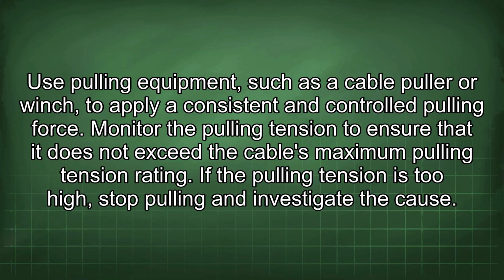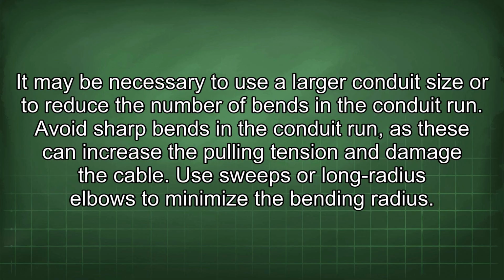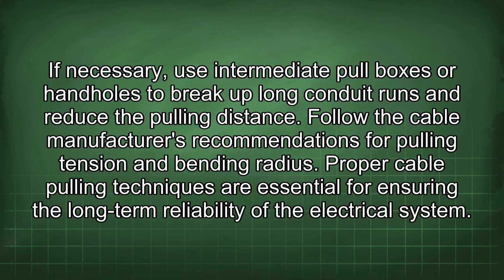Monitor the pulling tension to ensure that it does not exceed the cable's maximum pulling tension rating. If the pulling tension is too high, stop pulling and investigate the cause. It may be necessary to use a larger conduit size or to reduce the number of bends in the conduit run. Avoid sharp bends in the conduit run, as these can increase the pulling tension and damage the cable. Use sweeps or long radius elbows to minimize the bending radius. If necessary, use intermediate pull boxes or handholes to break up long conduit runs and reduce the pulling distance. Follow the cable manufacturer's recommendations for pulling tension and bending radius. Proper cable pulling techniques are essential for ensuring the long-term reliability of the electrical system.